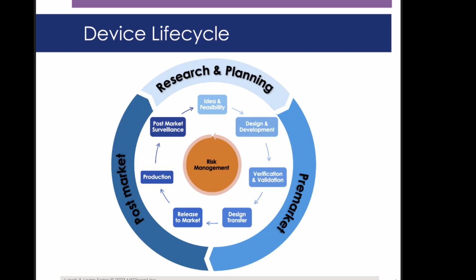The device will undergo any required regulatory review for the markets that it will be sold. With regulatory clearance or approval obtained, the device will be commercialized and released to the market. This kicks off the post-market phase. As you can see, post-market surveillance is a part of the device's life cycle, which links to the risk management and design and development processes.